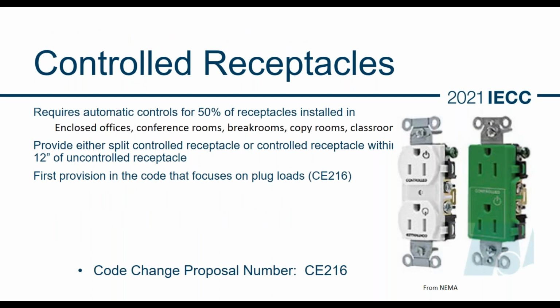One proposal, and I think this is the third time through of trying to get this in, is to have it so that the receptacles in offices and break rooms and copy rooms and classrooms can be turned off on a scheduled basis or through occupant intervention. They're called controlled receptacles. When you look at a commercial building, we have requirements for the building envelope, mechanical system, and lighting system. We have a lot of controls for mechanical and lighting. And when we start looking at the energy use in a typical commercial building, the energy use for those features is going down, but plug loads, essentially things that we plug into outlets, are becoming a larger and larger piece of the energy use pie.